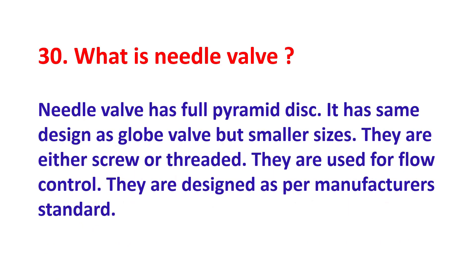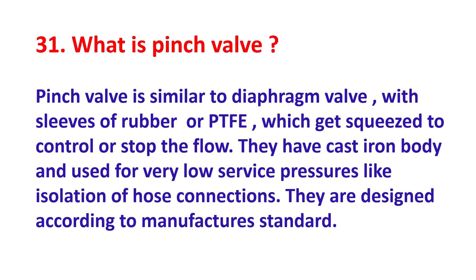What is a needle valve? A needle valve has a full pointed disc. It has the same design as a globe valve but in smaller sizes. They are either screw or threaded type and are used for flow control, designed as per manufacturer standard. What is a pinch valve? A pinch valve is similar to a diaphragm valve with sleeves of rubber or PTFE which get squeezed to control or stop flow. They have a cast iron body, used for very low pressures such as isolation of hose connections, and are designed according to manufacturer standard.